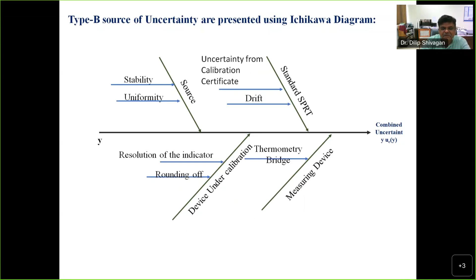From the standard side, the uncertainty of the calibration certificate that we have from the reference, drift, resolution of the indicator, because the DUC will also have a separate indicator and its corresponding rounding, and the thermometry bridge if we are using it for very high level measurements. Resolution is very important, because we see very different examples. People claim that they get very good uncertainties, but the required infrastructure at their end is very different. There are different probability distribution functions. Don't worry about this. In temperature, dy by dx phenomena happens: if you change any parameter, correspondingly your other measurement parameter will vary. We always use rectangular distribution for type B parameters, and for type A, of course, it is normal distribution in all cases, whatever measurement you have.